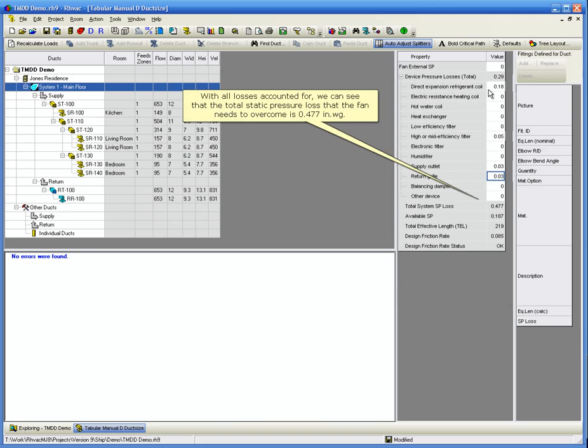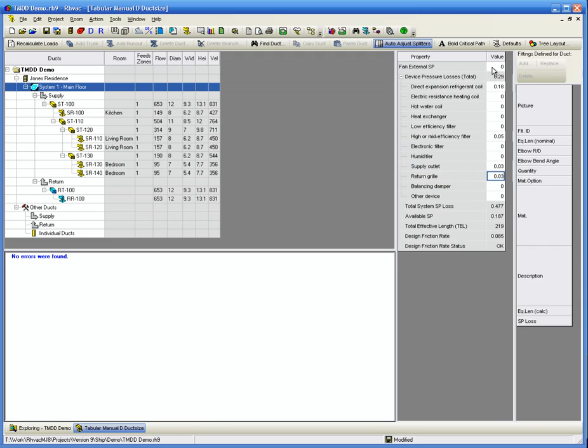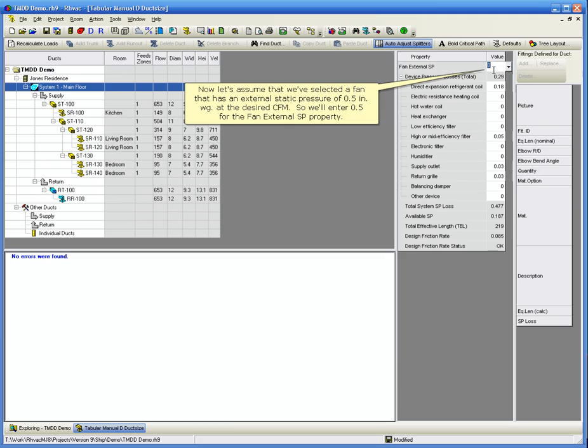With all losses accounted for, we can see that the total static pressure loss that the fan needs to overcome is 0.477 inches water gauge. Now let's assume that we've selected a fan that has an external static pressure of 0.5 inches water gauge at the desired CFM. So we'll enter 0.5 for the Fan External Static Pressure property.